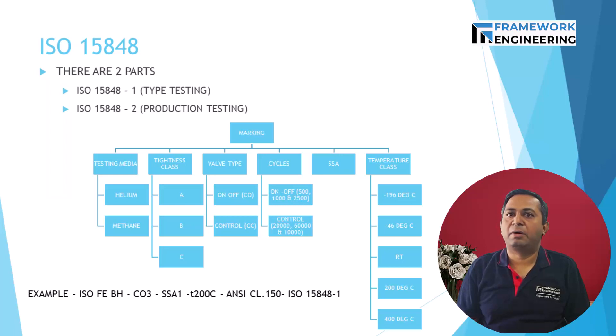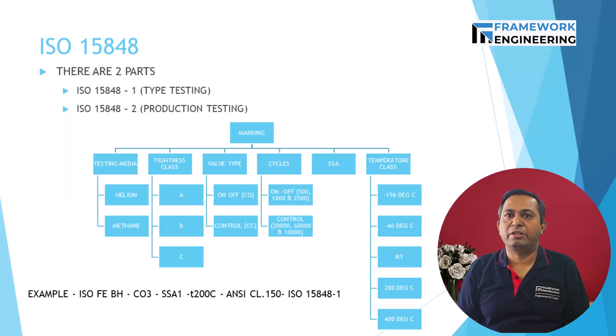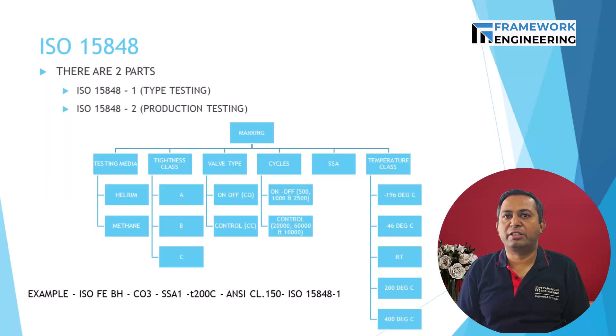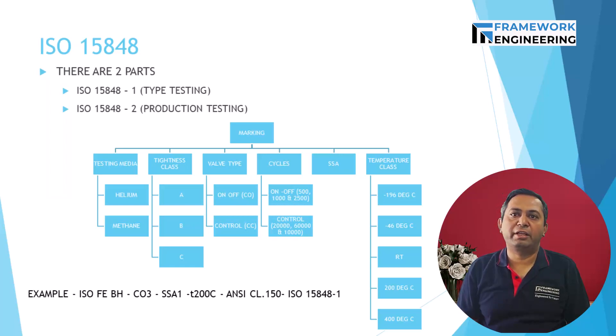As you can see in an example, a marking is done to indicate the complete details of the fugitive emission testing. For example: BH means tightness class B with helium as testing media; CO3 means it is an on-off valve with 2500 cycles; SSA1 means one stem seal adjustment done during testing; and T200 means the temperature class is 200 degrees centigrade. Followed by the rating and the applicable standard.